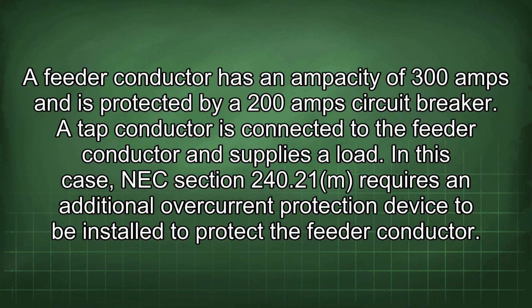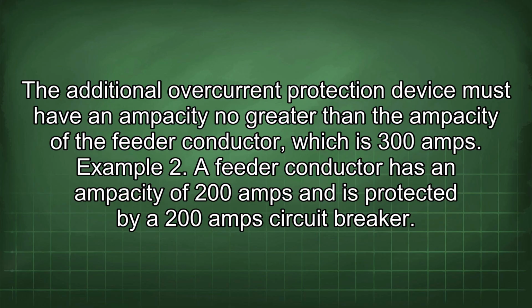Example 1. A feeder conductor has an ampacity of 300 amps and is protected by a 200 amp circuit breaker. A tap conductor is connected to the feeder conductor and supplies a load. In this case, NEC Section 240.21 requires an additional overcurrent protection device to be installed to protect the feeder conductor. The additional overcurrent protection device must have an ampacity no greater than the ampacity of the feeder conductor, which is 300 amps.